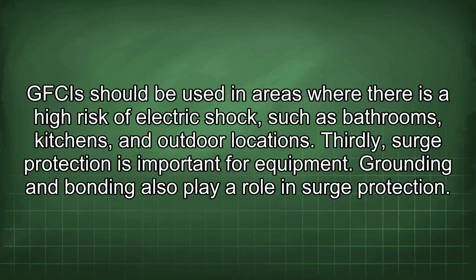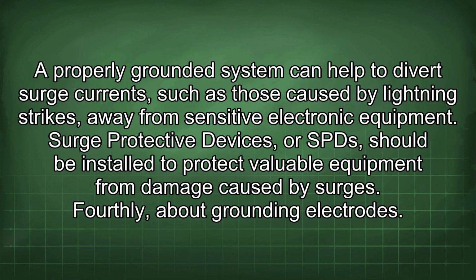Grounding and bonding also play a role in surge protection. A properly grounded system can help to divert surge currents, such as those caused by lightning strikes, away from sensitive electronic equipment. Surge protective devices, or SPDs, should be installed to protect valuable equipment from damage caused by surges.